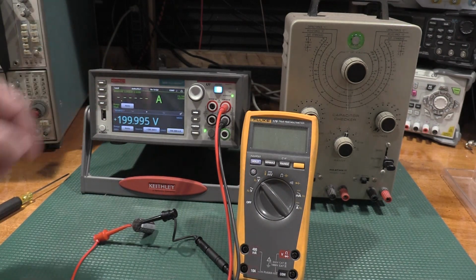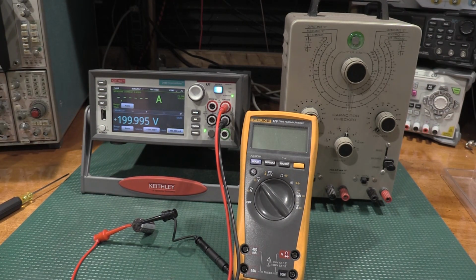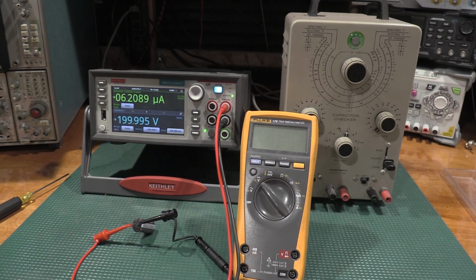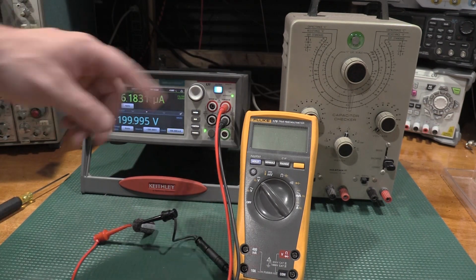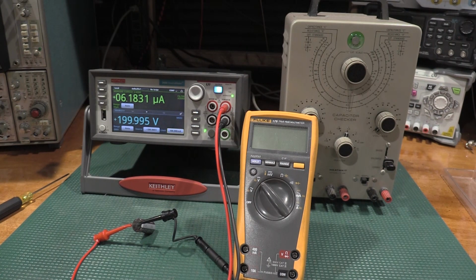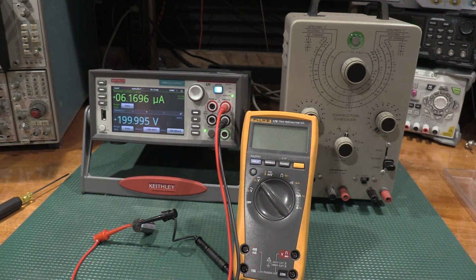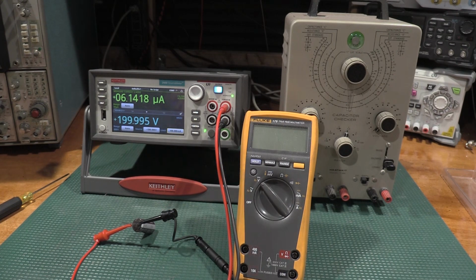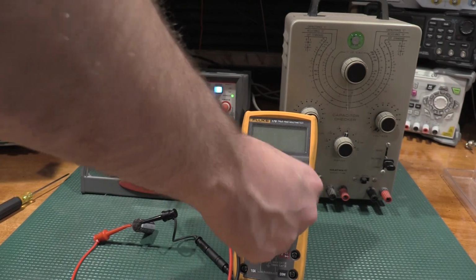Here we are on the voltage and current scale with the 10 power line cycles and the filtering. 6.2 microamps. This will continue to go down probably. Yeah, 183. It'll go down some more. 169. So yeah, it's continuing to go as it's going. So the longer it sits here and soaks, the better it's going to get. But it would probably get into the nanoamps, maybe even to the bottom of the nanoamps if I gave it enough time. But that should be good for demonstration purposes.